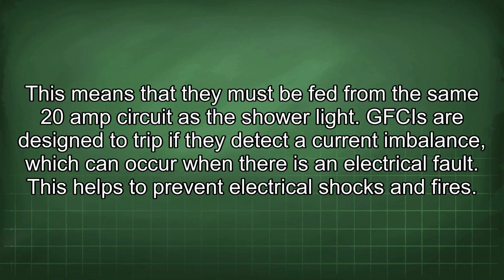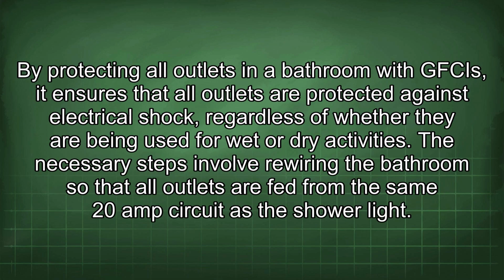This means that they must be fed from the same 20-amp circuit as the shower light. GFCIs are designed to trip if they detect a current imbalance, which can occur when there is an electrical fault. This helps to prevent electrical shocks and fires. By protecting all outlets in a bathroom with GFCIs, it ensures that all outlets are protected against electrical shock, regardless of whether they are being used for wet or dry activities.